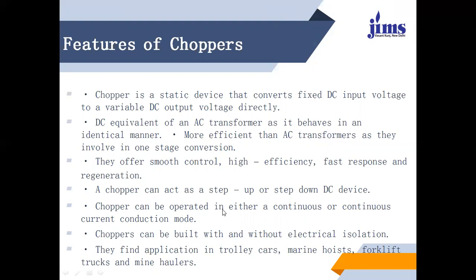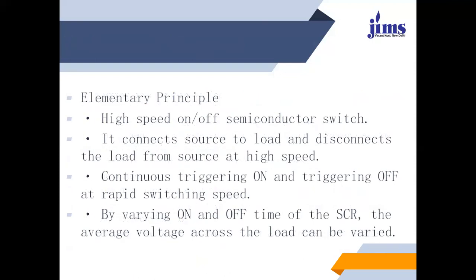Choppers find application in trolley cars, marine hoists, forklift trucks, and mine haulers. They provide a high speed on or off semiconductor switch that connects the source to the load and disconnects the load from the source at high speed. By triggering on and off at rapid switching speed, varying the on and off time of the SCR, the average voltage across the load can be varied. These are the elementary principles on which DC choppers operate.